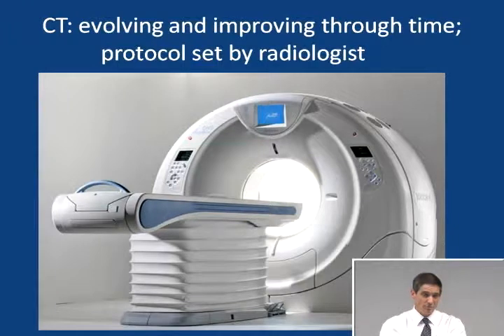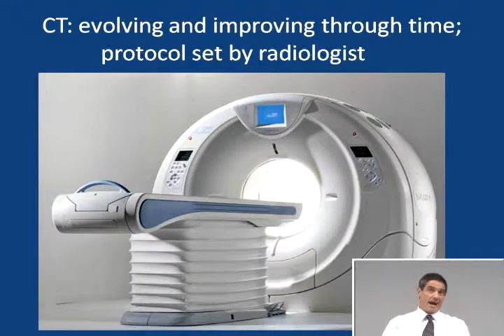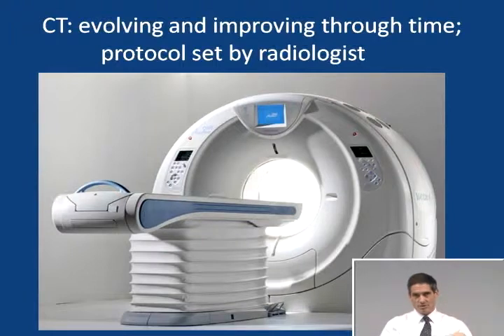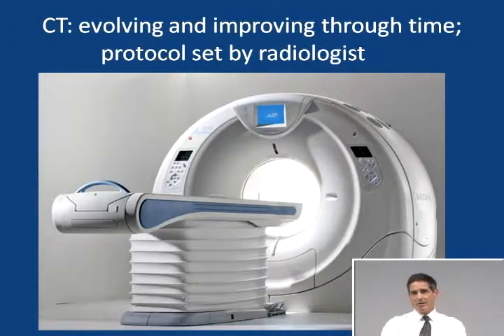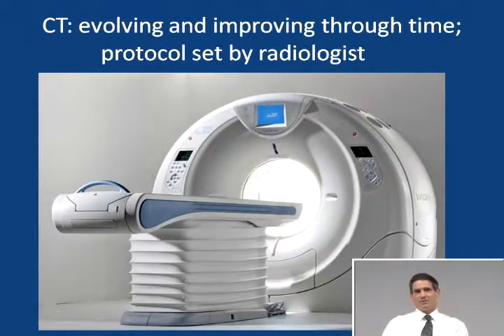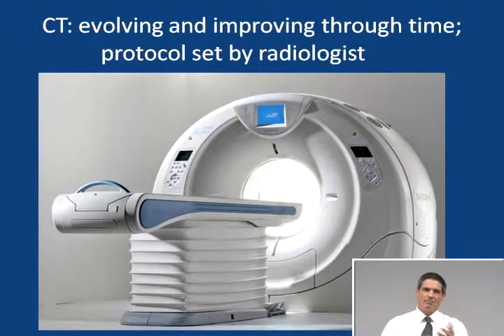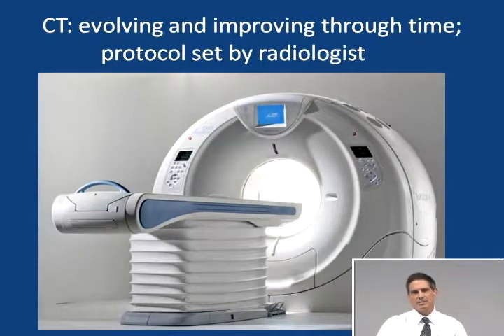In addition to thinner slice thicknesses and reconstruction techniques, the time required to do a scan dropped from an hour or more down to a few seconds. Most of the time, scanning a patient now is really just prepping the patient, waiting for oral contrast to go through the GI system, waiting for IV contrast to go through the circulatory system, and getting the patient on and off the table. Scanners continue to evolve — 64, 128, and now 320-slice capabilities allow cardiac work that will probably supplant coronary angiography and echocardiography, and also allow better vascular work including stroke evaluation and triage for intraarterial thrombolysis.